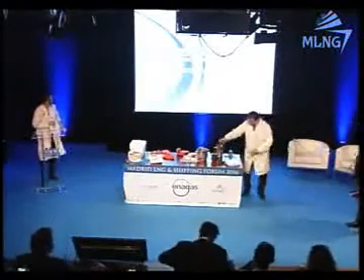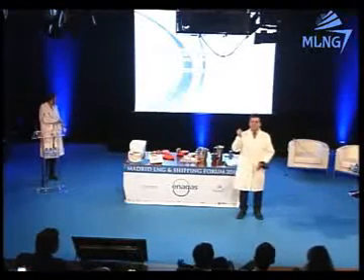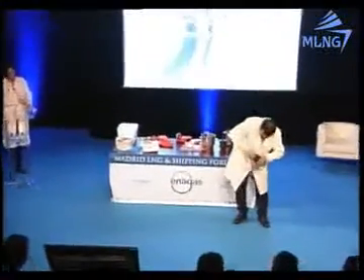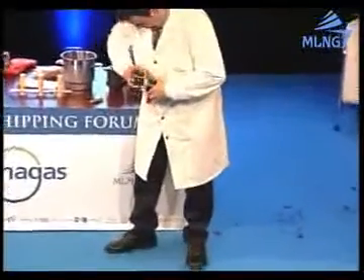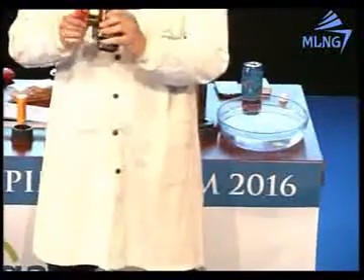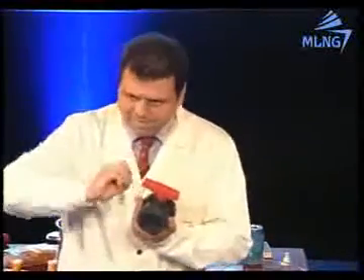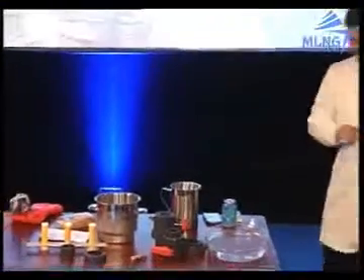Sorry. I have to tell you the secret. The Spanish solution to the ball valves. The Spanish solution is to drill the ball, like this. If we put here a little hole, this small hole is the solution, the Spanish solution. And this is a safe valve, because through this little hole, the vapor goes to the pipe, to the safe vessel. Okay, thanks a lot. Okay, thank you, Javier.